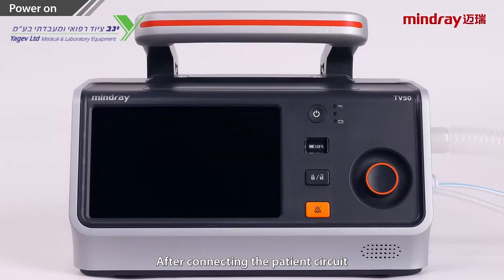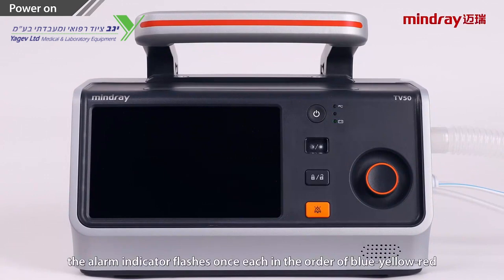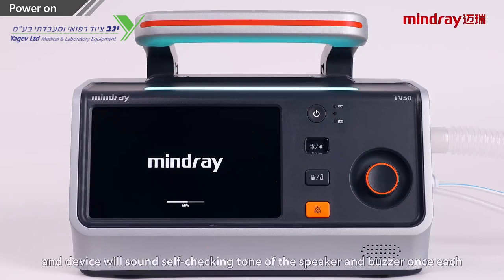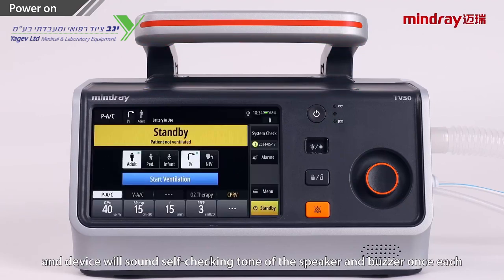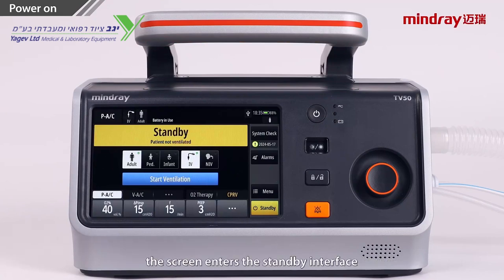After connecting the patient circuit, press the power on button to turn on the power. The alarm indicator flashes once each, in the order of blue, yellow, red, and the device will sound the self-check tone of the speaker and buzzer once each. The screen then enters the standby interface.